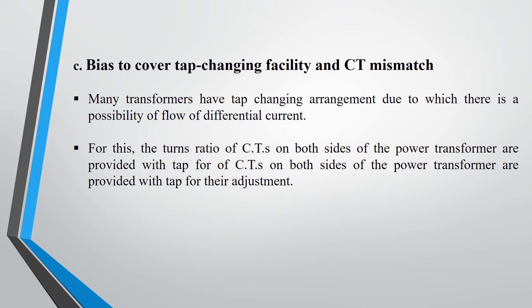The third consideration is bias to cover tap changing facility. We know that some transformers have a tap changing arrangement so that voltage control can take place. In this, the turn ratio of the CT on both sides of the power transformer is also provided with a tap to get adjusted with the tap setting arrangement of the transformer.